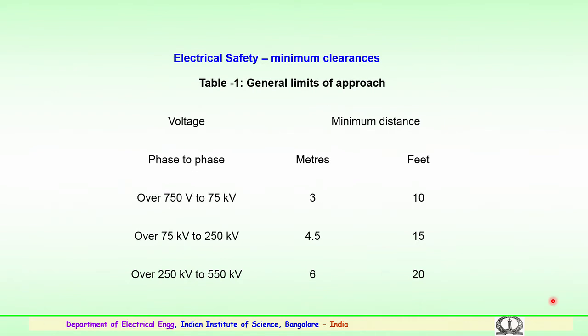So, the safe electrical minimum clearances as per the standards, the limits of the general approach for electrical safety, are given here. You can see the voltage and the minimum distances which are mentioned. This is the phase to phase voltage level, the distance in meters and the distance in feet. So, you can see that over 750 volts, when the personnel is trying to work in an area up to 75 kilovolts, he should have a minimum clearance of 3 meters or about 10 feet, to be followed as per the safety rules. In case the equipment or the lines are of 75 to 250 kilovolts, a minimum distance of 4.5 meters or 15 feet has to be allowed and maintained.